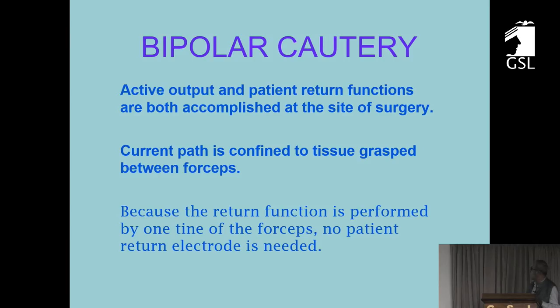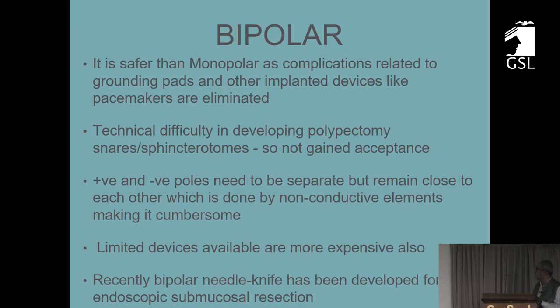In bipolar, active output and patient return functions are both accomplished at the site of surgery. Current path is confined to tissue grasped between the tines of the forceps. Because the return function is performed by one tine of the forceps, no patient return electrode is required. It is safer than monopolar, as complications related to grounding pads and other implanted devices like pacemakers are eliminated.